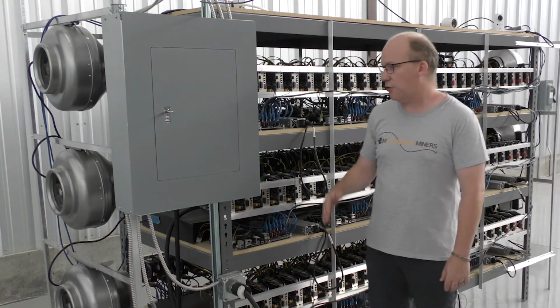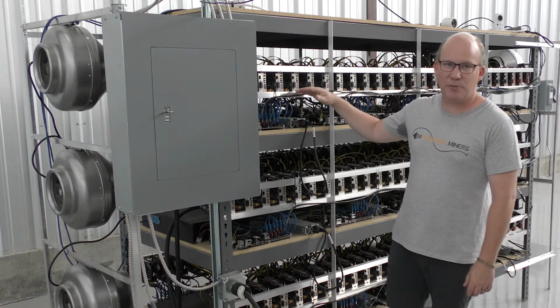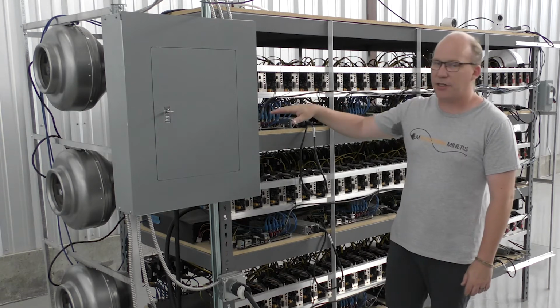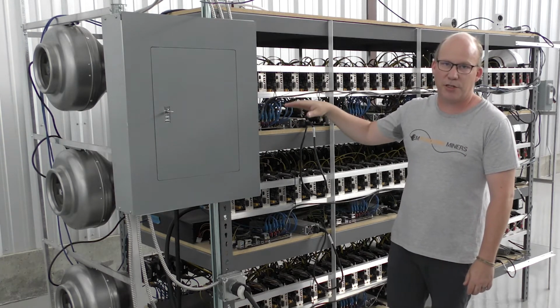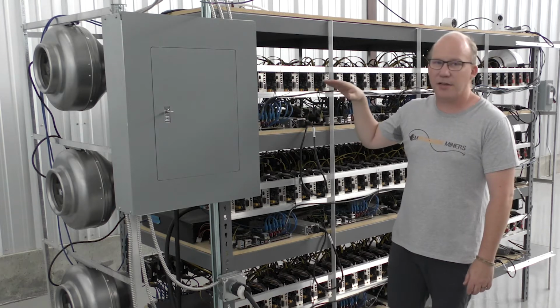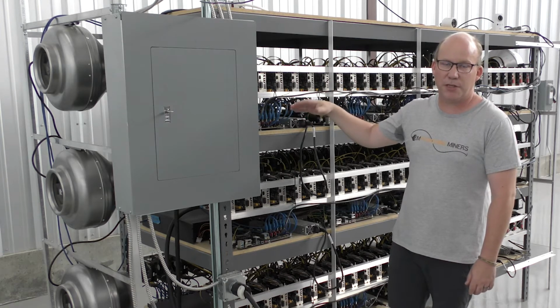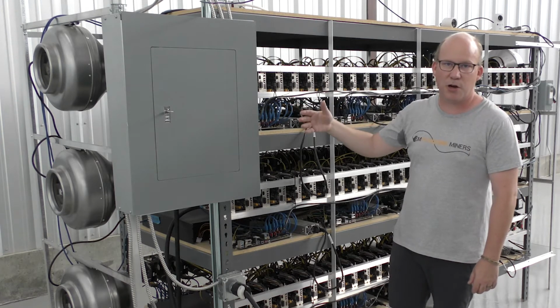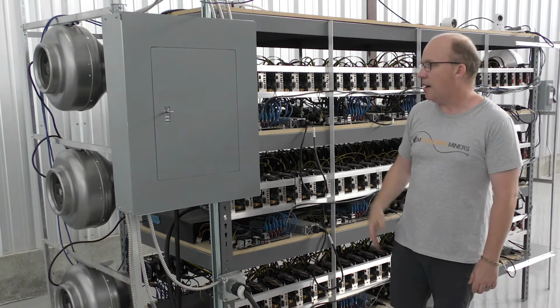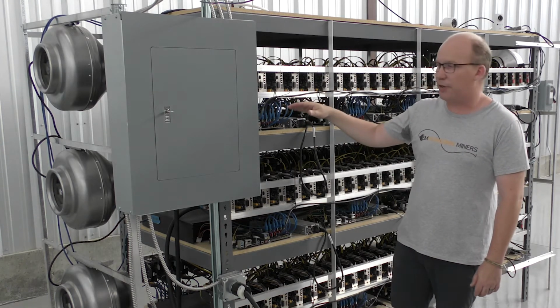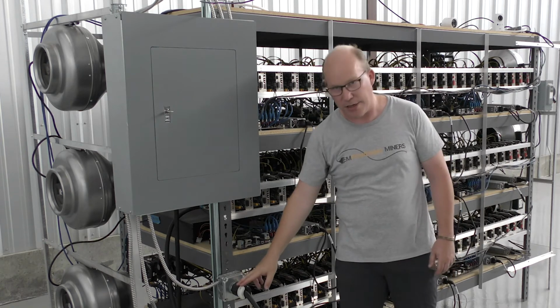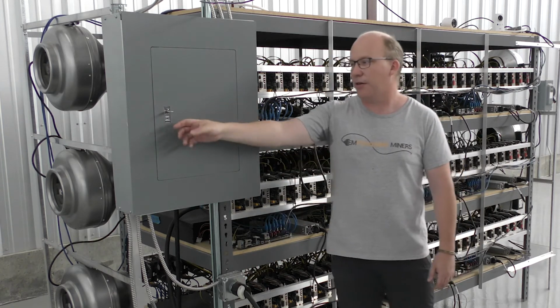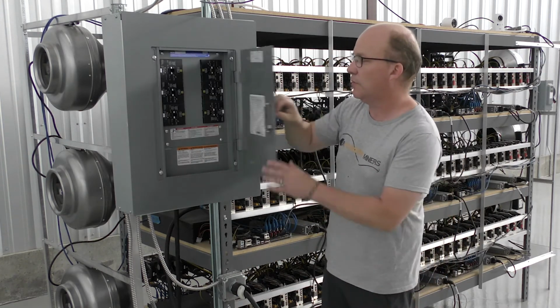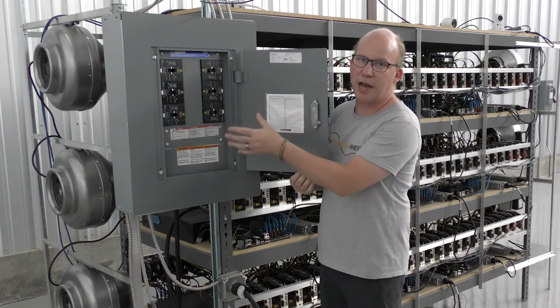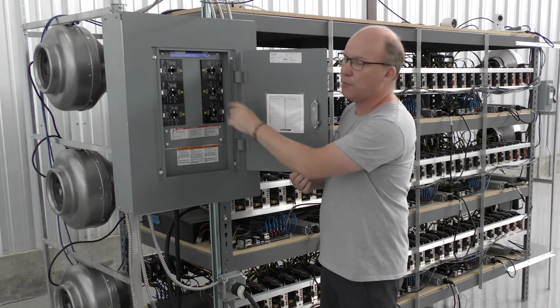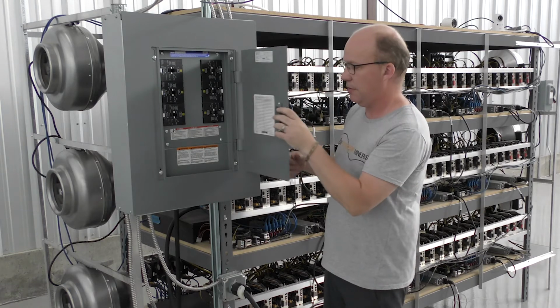So each shelf has 9 machines on it. It's connected to our New School Mining's 9-port smart PDU that lets us easily control these systems remotely through a smart web interface. That PDU connects to an outlet here, which goes to a breaker in the breaker panel. The breaker panel drives 2 racks, so 1 breaker per shelf, basically, in there.